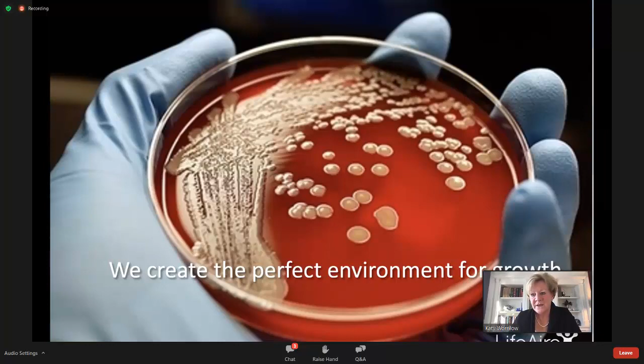So as a random QC, I personally swabbed the ULPA filters above our IVF laboratory and was shocked when we got the report back from the micro lab that we had Bacillus growing on top of our ULPA filters. To put this in perspective, your HEPA filters or your ULPA filters are going to capture organics based upon size. As they capture the biologicals, those biologicals are not killed. They will continue to grow.